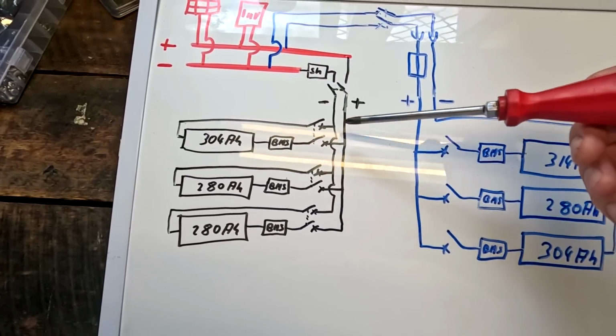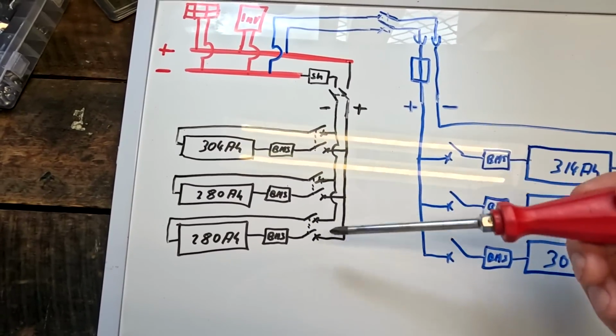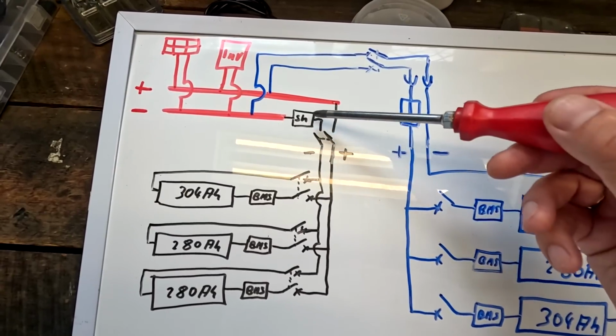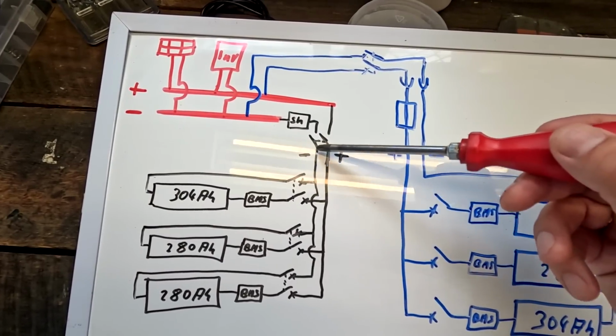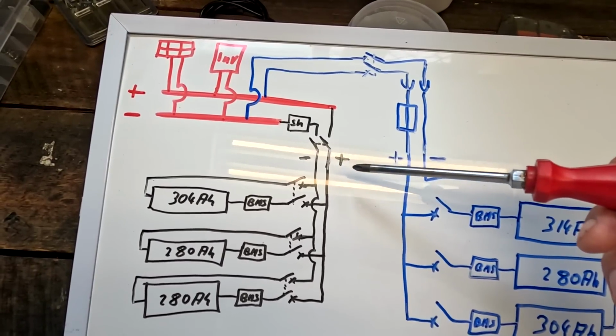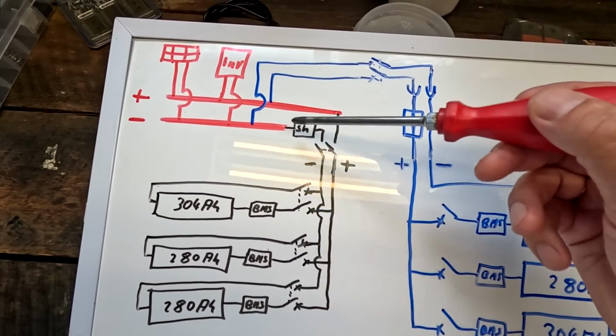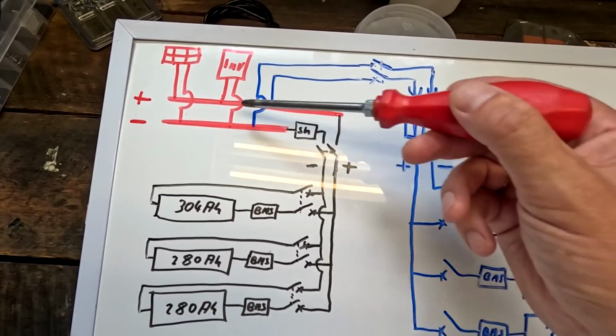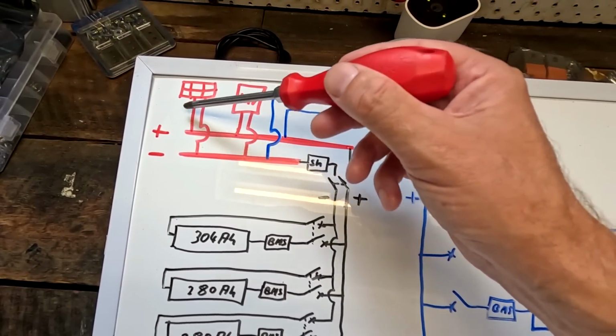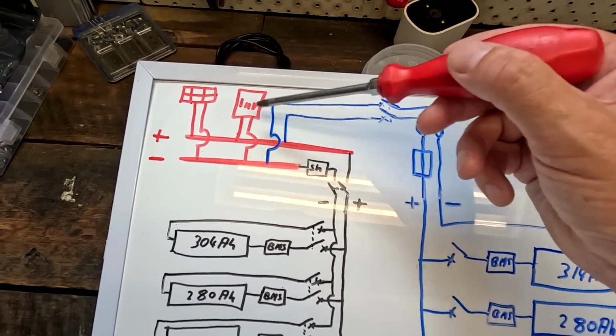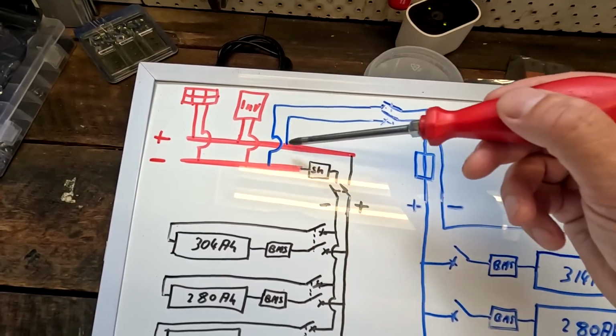This all feeds into the vertical bus bar system. I made a bit of a mistake here because the shunt actually comes first, and then we have another double pole circuit breaker before we connect these 3 batteries in parallel to the main bus bar system at the top. This is where the solar system is connected with the MPPTs, and also the inverter and the second inverter and all our other loads. Everything is connected to this main bus bar system at the top.